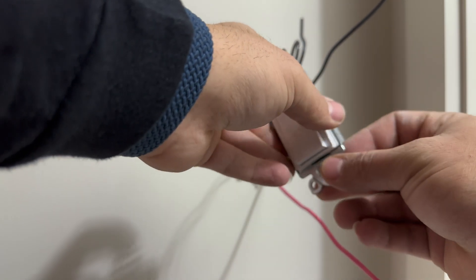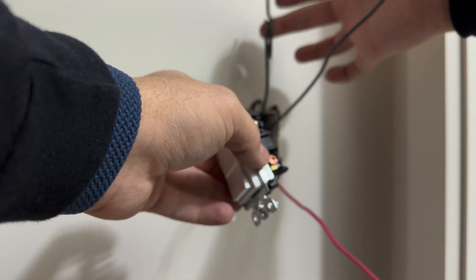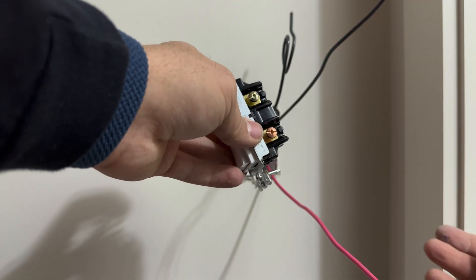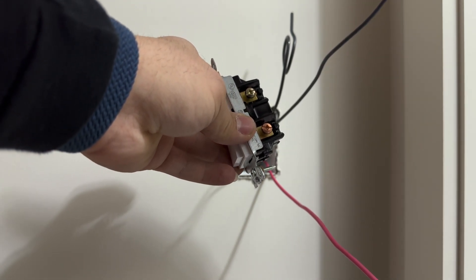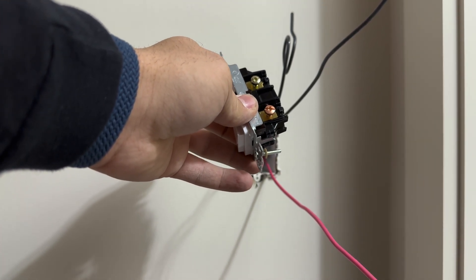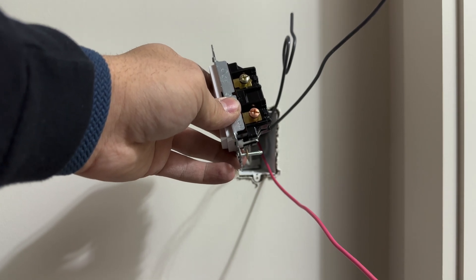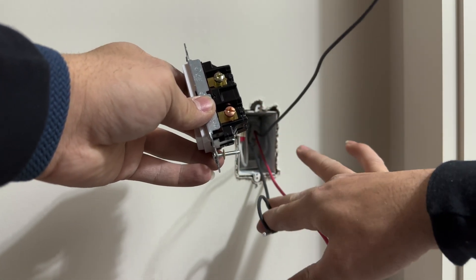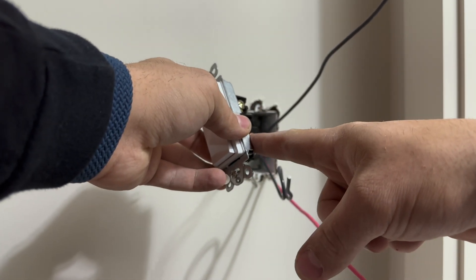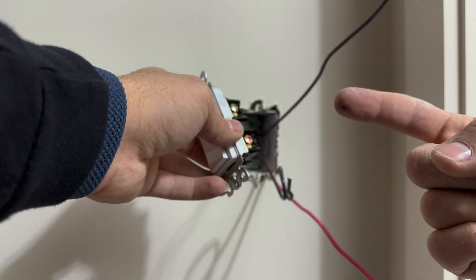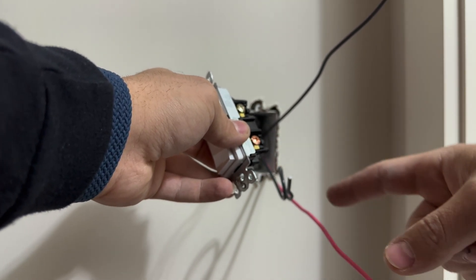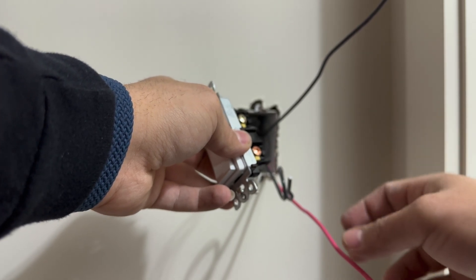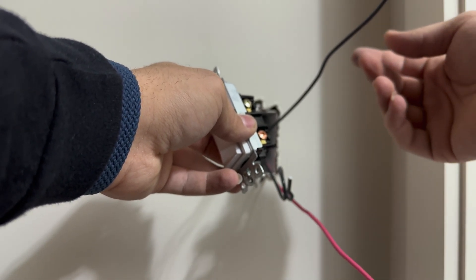Because the switch leg is on this side and the power will be on the other box where the other three-way switch is connected, the switch leg will go in the common screw and in the other three-way the power will go on the common screw, so it's sort of like upside down.